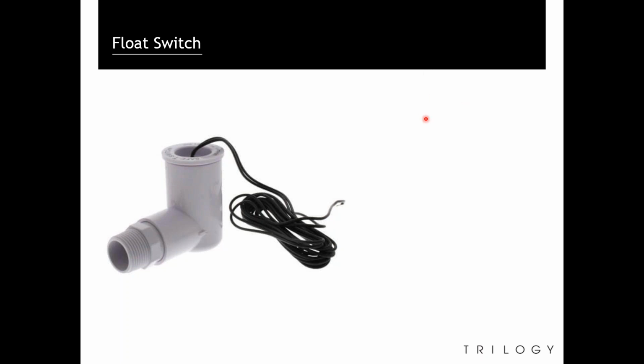Our float switch. The float switch will shut down the power to the unit to prevent water from leaking. It's plumbed into the condensation drain to detect water. It's wired on the inside of the furnace to the red 24-volt thermostat wire. So if it senses water, it just shuts down your furnace.